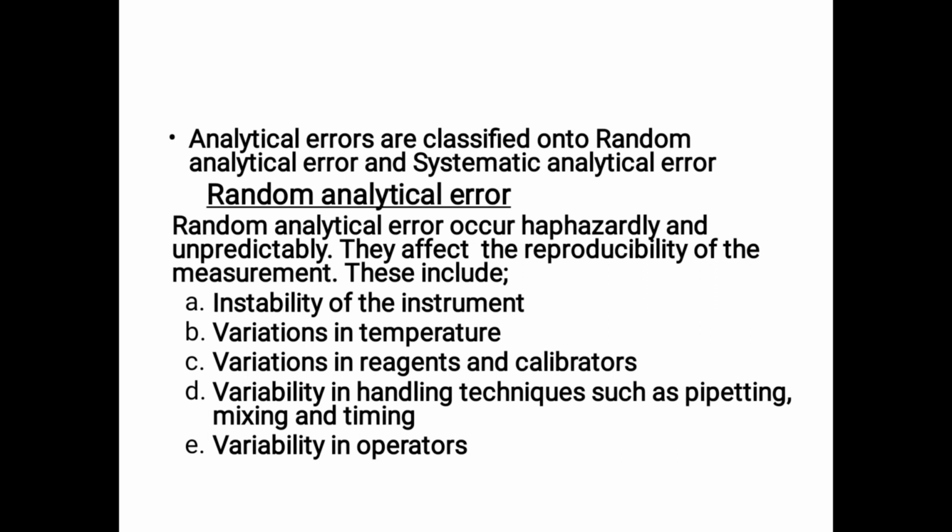See, random error, as the name indicates, is random. It occurs haphazardly and unpredictably, meaning suddenly or without our knowledge. They affect the reproducibility of the measurement. What is reproducibility? Suppose my blood sugar is 100 on a particular Cobas machine. If I put the same sample after 2 minutes, I am supposed to get 100 or 99. Again after 5 minutes I should get 101 or 100. So repeated same values is reproducibility.